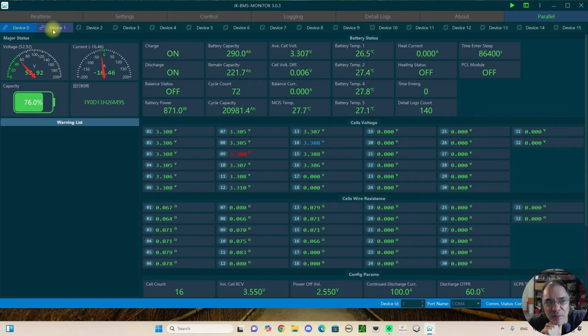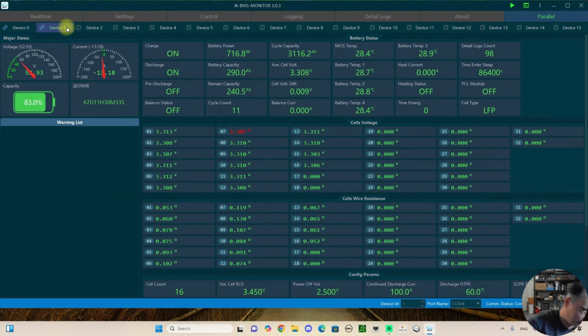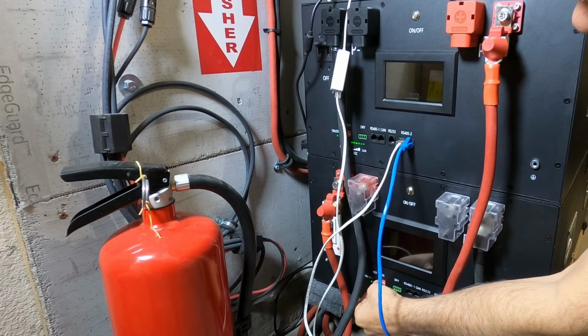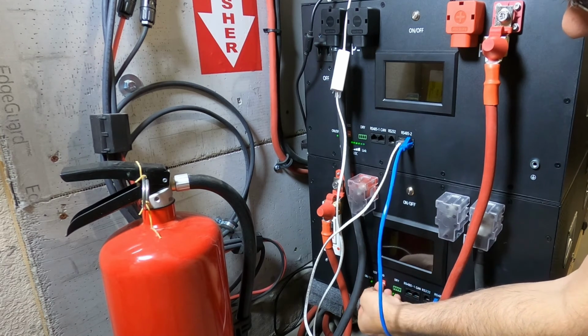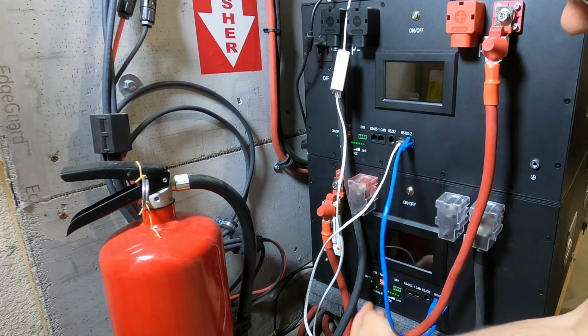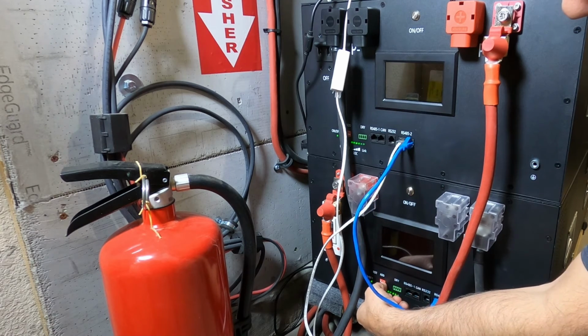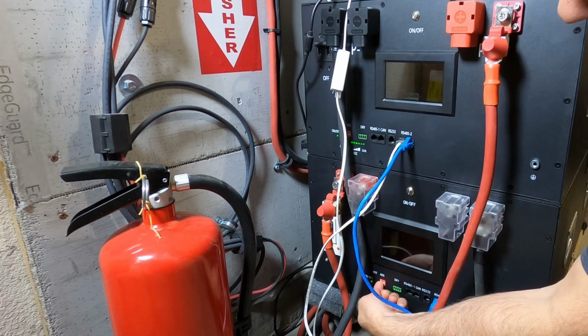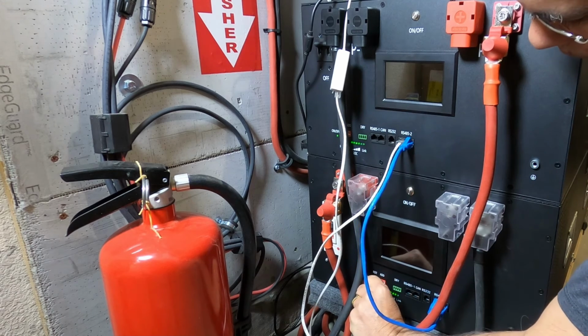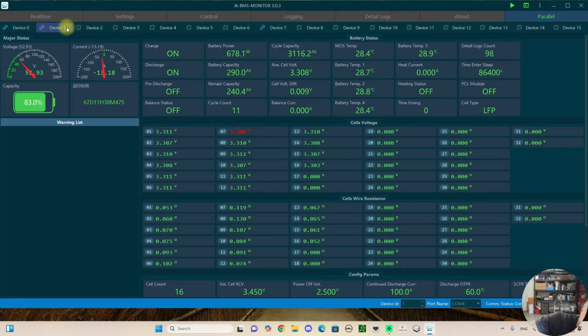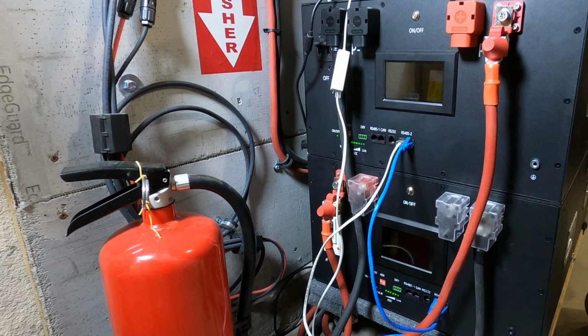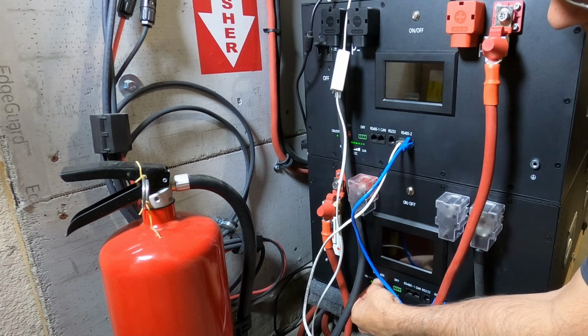So right now my slave is on device 1 - dip position 1 is up and the rest are down. So I'm gonna put dip 1 up and dip 2 up, so we're 1 and 1. And watch what happens - look, it popped in over here, now it's number 7. So it's not gonna screw anything up if you just start playing around with it. It's that easy - I literally just figured it out by playing with the dip switches.